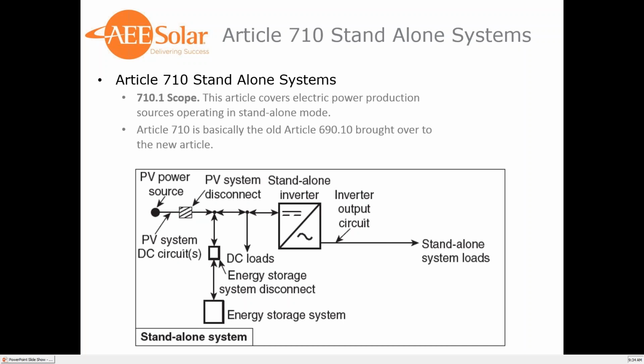The article is very small. Not too much detail in it. Just talks about details of labeling for 120 VAC loads, or if you only have a 120 VAC inverter. Voltage and frequency control. And also one thing to note too is, for these standalone systems, 690 only pertains up to the first PV system disconnect.